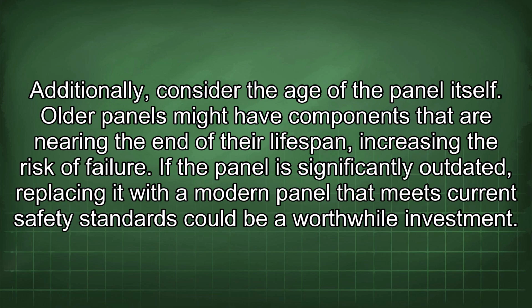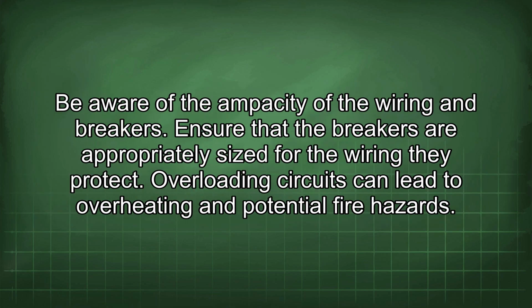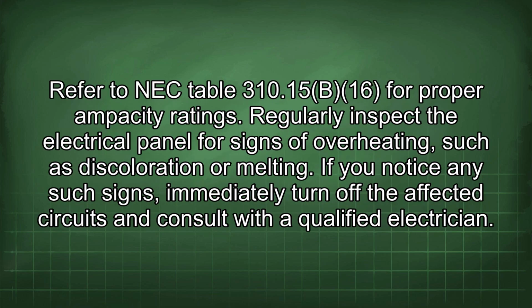If the panel is significantly outdated, replacing it with a modern panel that meets current safety standards could be a worthwhile investment. Be aware of the ampacity of the wiring and breakers. Ensure that the breakers are appropriately sized for the wiring they protect. Overloading circuits can lead to overheating and potential fire hazards. Refer to NEC Table 310.15(B)(16) for proper ampacity ratings.